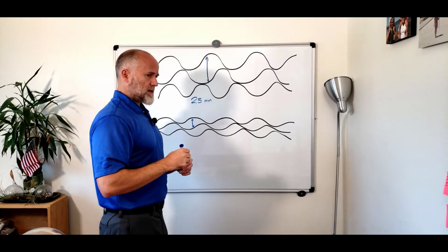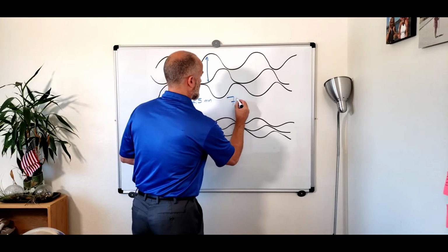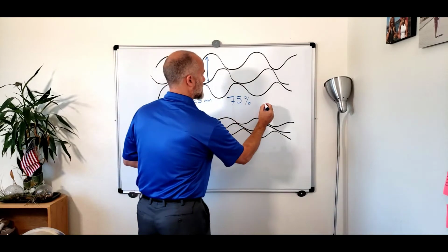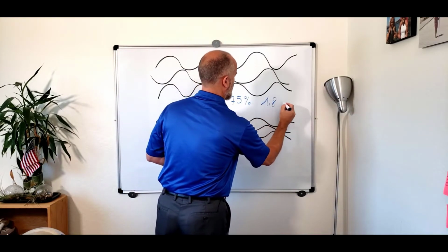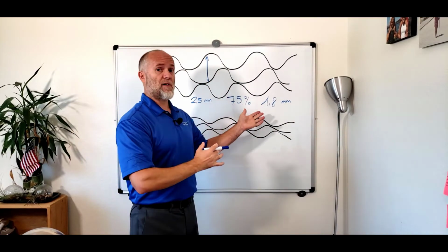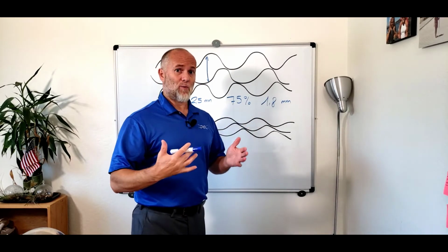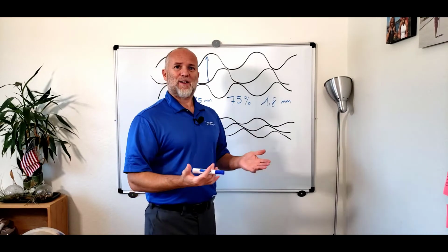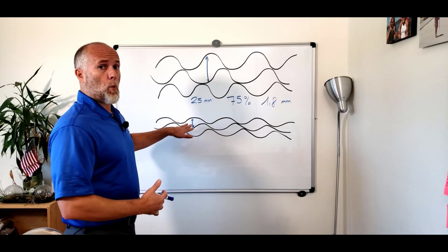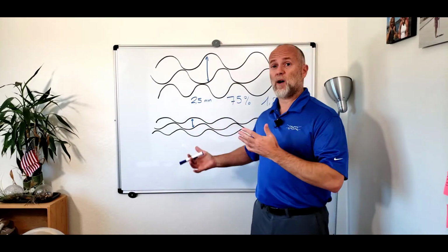We normally recommend that you don't have particles that exceed 75% of the size of the channels, which equals 1.8 and change millimeters. So once you know that you cannot have particles bigger than 1.8 millimeters going through your heat exchangers if you don't want to build them up, you design your mesh accordingly. And the same goes for here. Let's say that in this case this is 1.5 millimeters. You need to design your mesh in the strainer for particles that are around 1 millimeter.